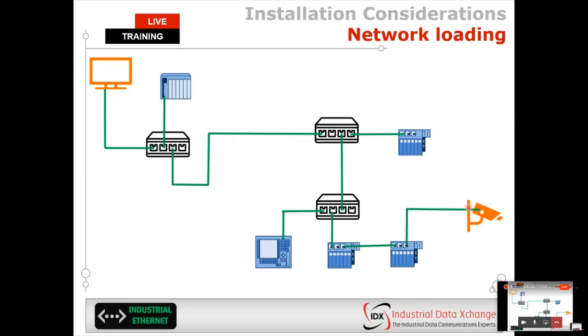That's very interesting - I can actually link lots of different network components in the same Ethernet infrastructure. Even if this network is PROFINET or Modbus TCP, they can share the same common backbone or Ethernet connections to share multiple different protocols, from PROFINET and Modbus TCP to UDP telegrams from a video camera that's monitoring my process or conveyor system to check for breakages or blocks.